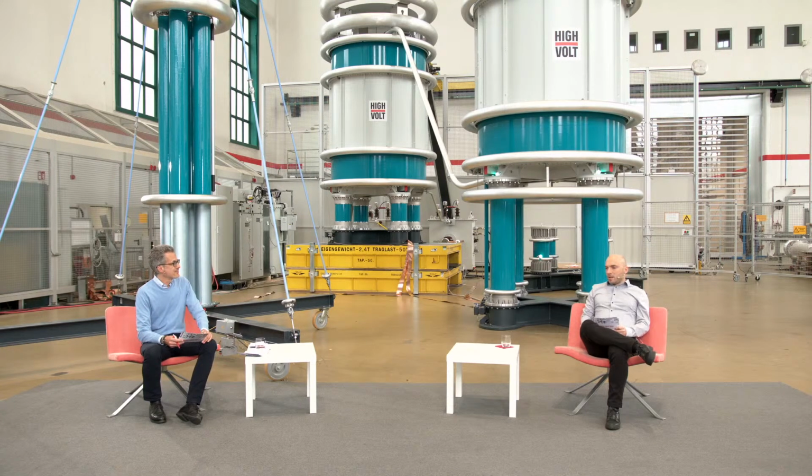Yes, we really believe that in combination with big data and long-term measurements it will be possible to get some information about the aging condition, and also, as Marc mentioned, to predict with a certain plausibility. For example, there's a 60% chance that in the next 6 or 12 months this joint will fail. So we suggest changing this joint in the next downtime, which is planned anyway, just to reduce your risk. And this will definitely be possible in our opinion.